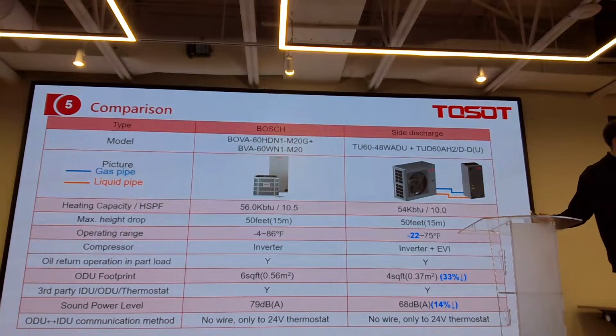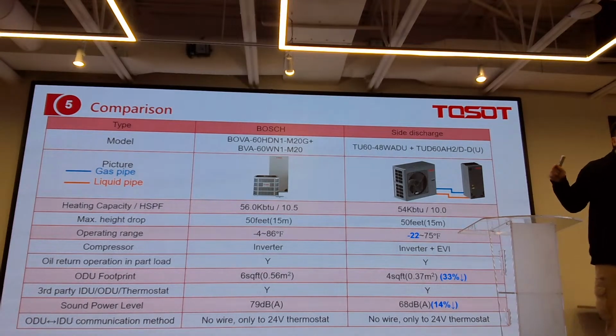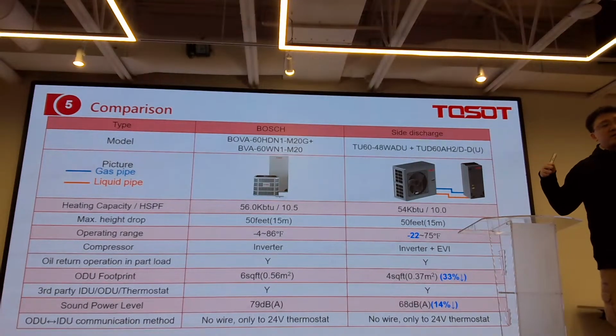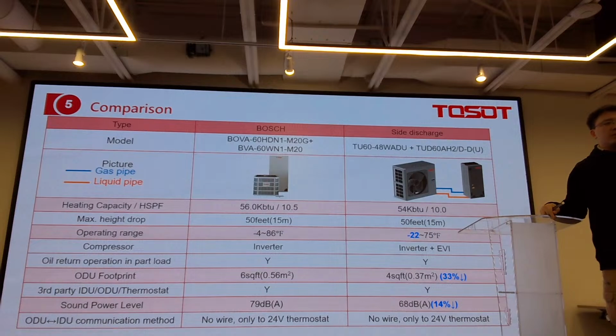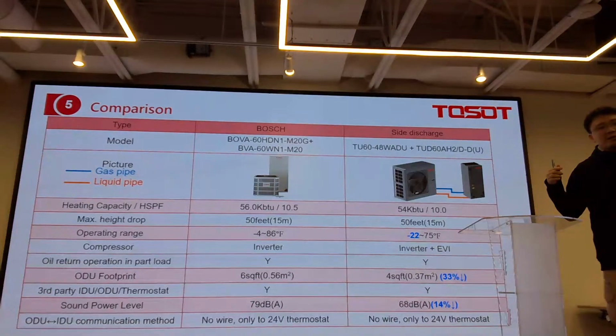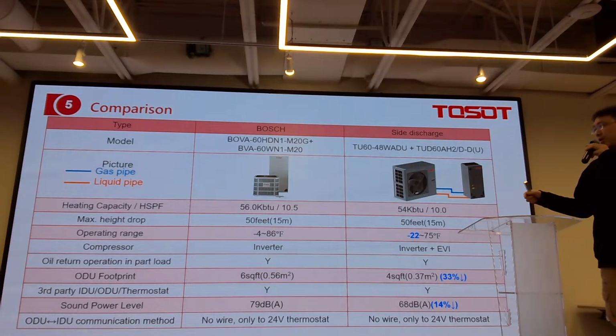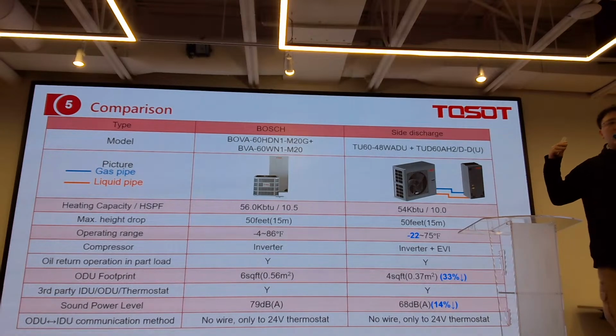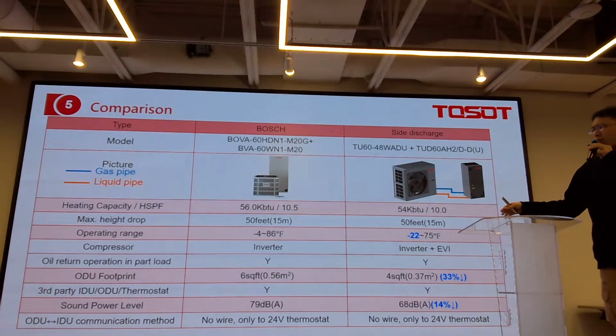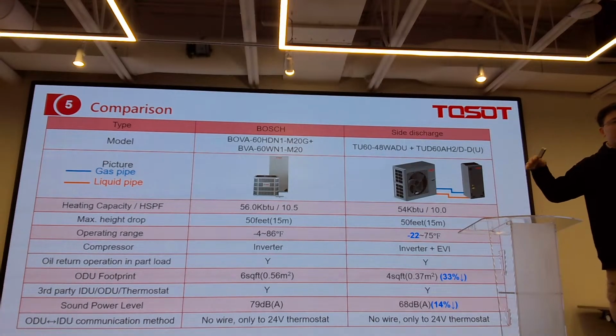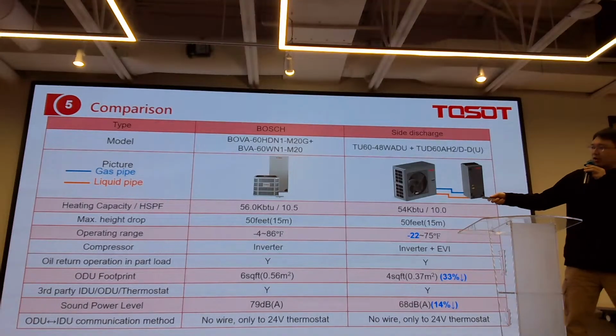Do you know why? For the on-off compressor, there's no oil return, but for the inverter compressor, there is always an oil return operation. The reason is that with the inverter, we can lower the compressor frequency. For a long time operation at a low frequency, we're afraid that too much oil will be trapped on the indoor side, which means the compressor will be short of oil and then it will burn out easily. So to prevent this, we require the inverter compressor to go to a high frequency during the oil return operation, then flush the oil trapped in the indoor side to flow back to the outdoor. And that is the oil return.